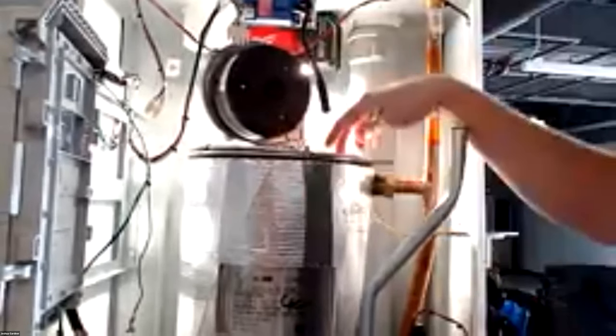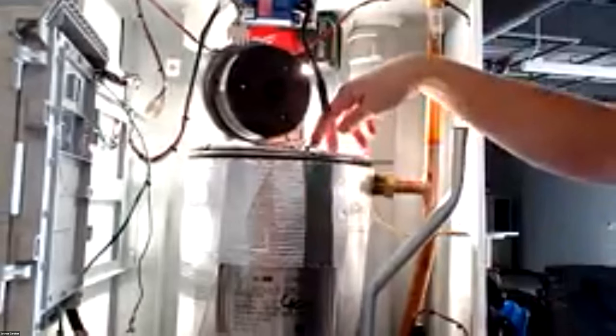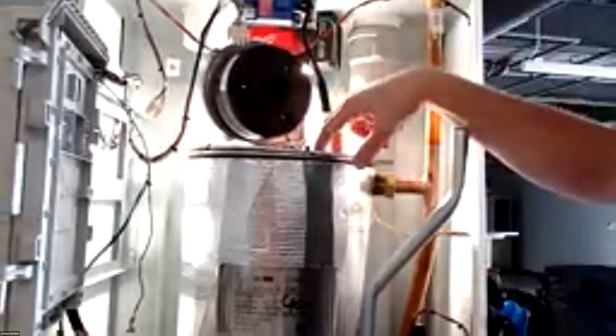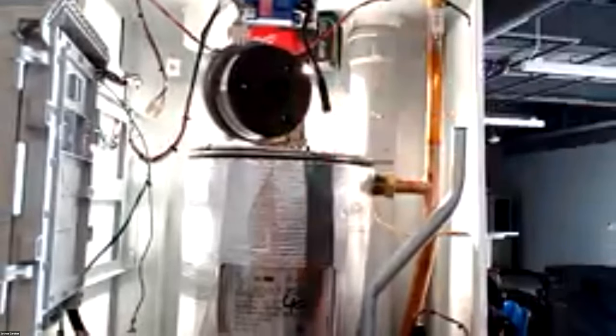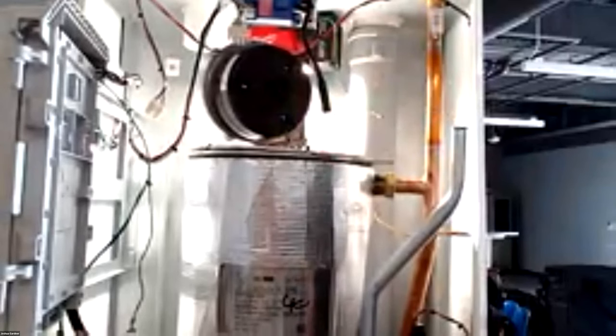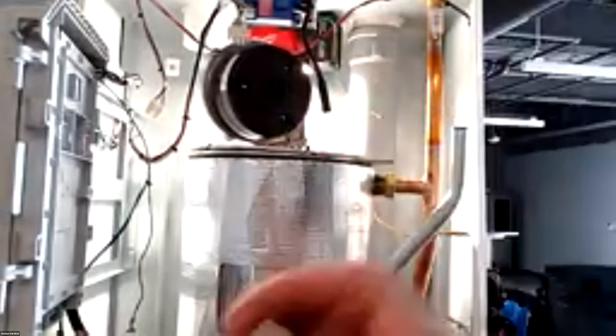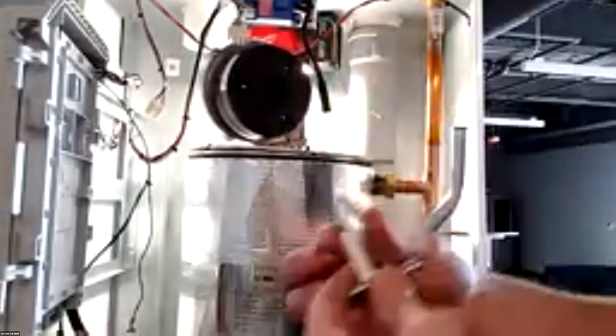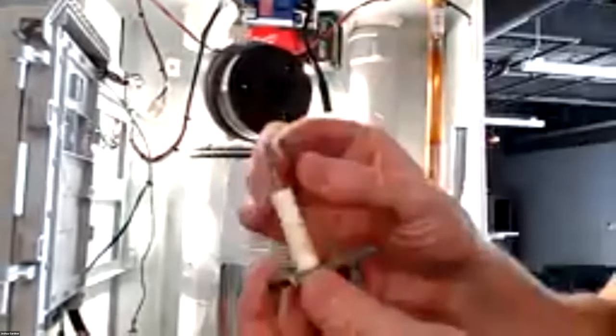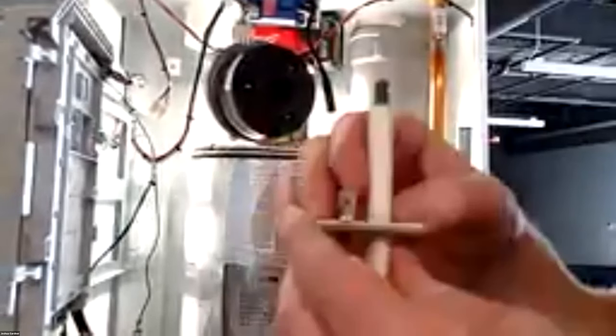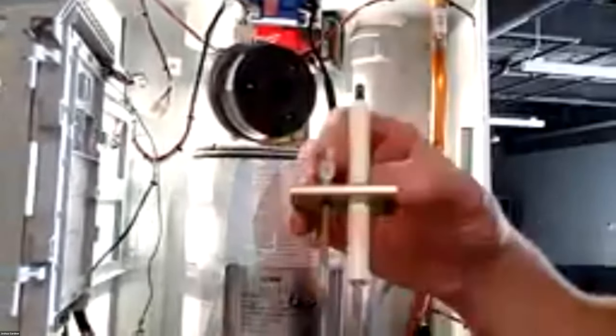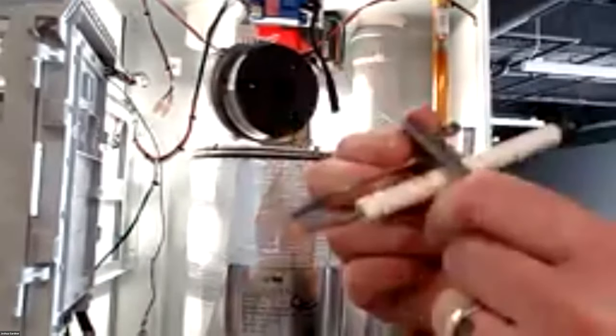And that igniter too, I'd probably torque. The igniter's just gotta be snug. Get it down there snug, do like a half turn and that's it. You don't wanna go too much with that igniter because if we go really hard, we could possibly deflect or move the distance in our igniter. So you just want that snug down where it's not gonna leak, but we're not trying to over tighten that. So we smush out the gasket and we have metal on metal.